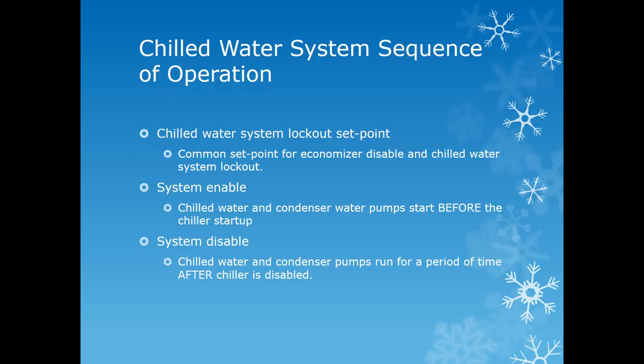Part of the chilled water system sequence of operation is the chilled water system lockout set point. That set point is a temperature value at which the chiller is either enabled or disabled. It is very helpful to set the chilled water lockout to the same value as the economizer set point of your air handlers. Whenever the chilled water system comes up we disable the economizers of the air handlers and close them to outside air to allow the system to be cooled by the chiller only. When the outside air temperature reaches or falls below the lockout set point, the chilled water system is disabled, allowing outside air to be used through the air handler to cool the building.